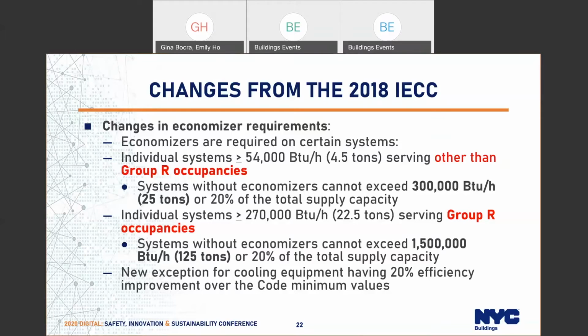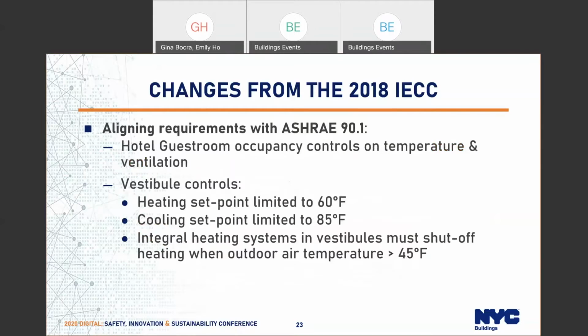It has to be a 20% improvement over the code minimum, and that's the EER value, not the IEER. So it's the full rated value, not the part load value. ASHRAE allows either one, but IECC only allows the full load value. Other changes in the HVAC section, there was some alignment with the 2018 IECC with ASHRAE 90.1.